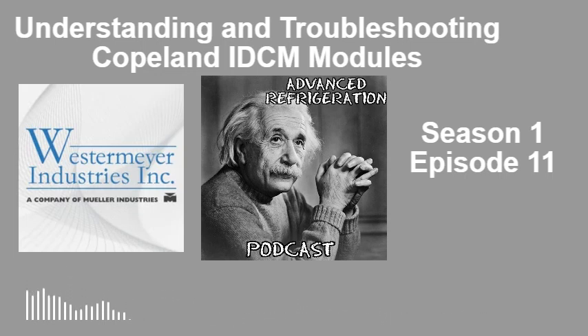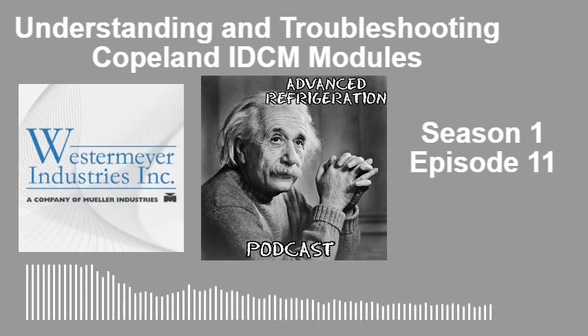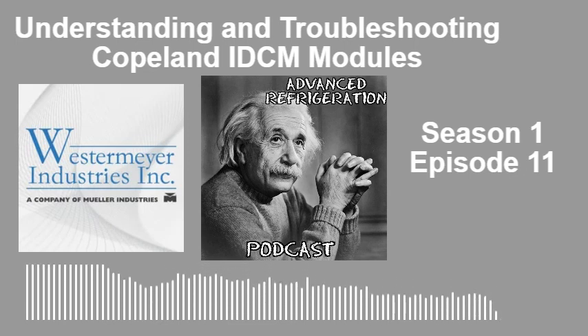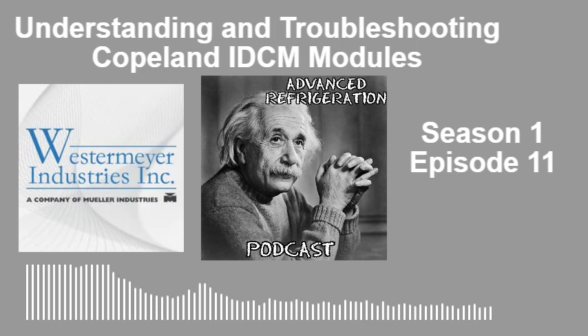Now, if that is not set up properly, say if you set that minimum to 0, you would have nonstop nuisance demand signal loss alarms, which I see a lot on new startups.